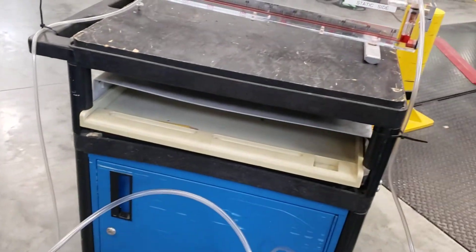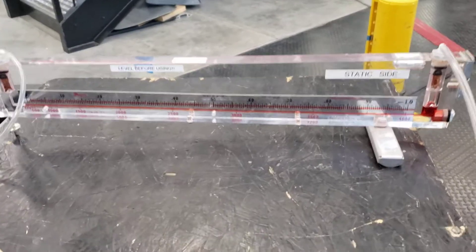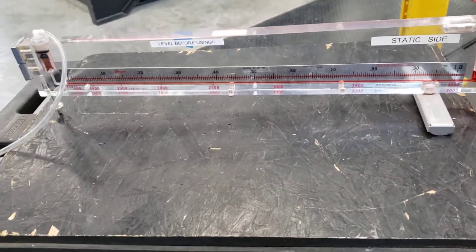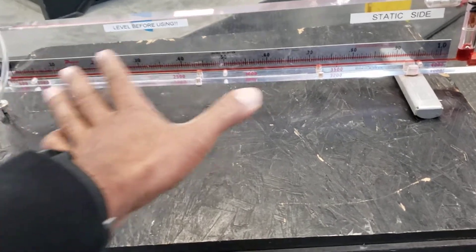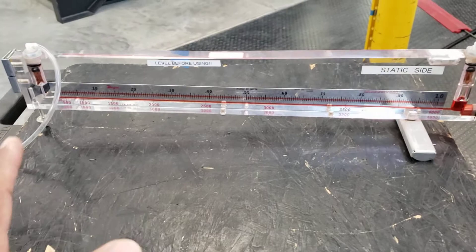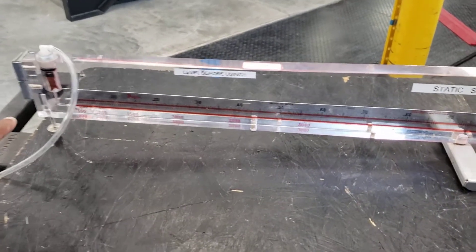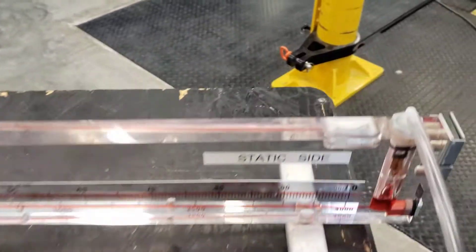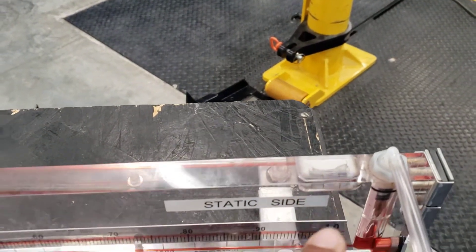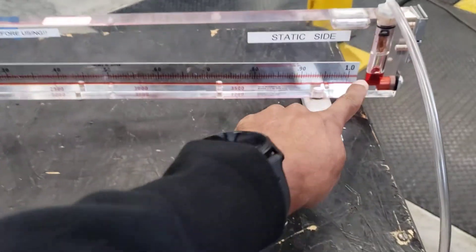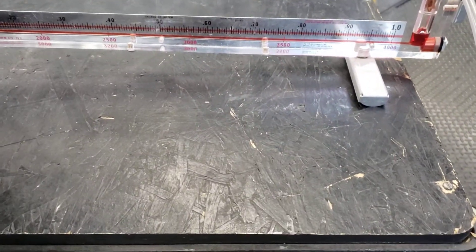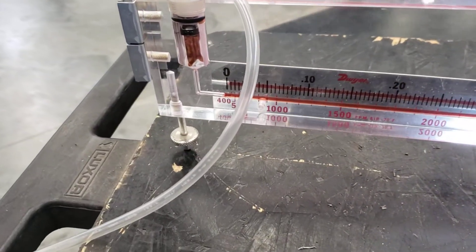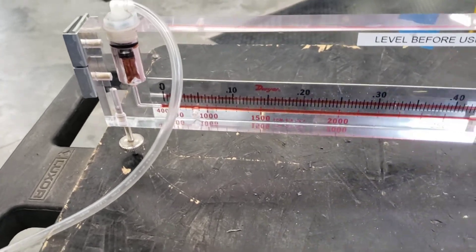Now we have this manometer connected to an inclined manometer. Because it's water and this is simply air pressure, there will be not much difference, so this is only a one inch manometer. Before you start, you must level this piece. There is a screw there you can adjust and there is a level here, so make sure it's leveled first and that you have enough fluid. If it's leveled, this should be at zero right here. Right now it has zero reading, so everything is perfectly set up.